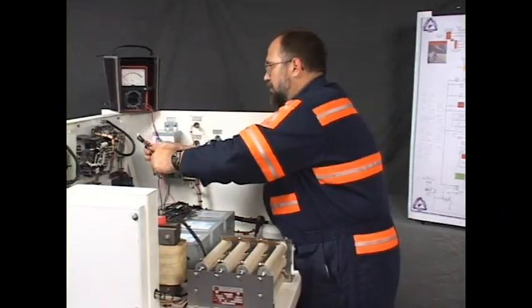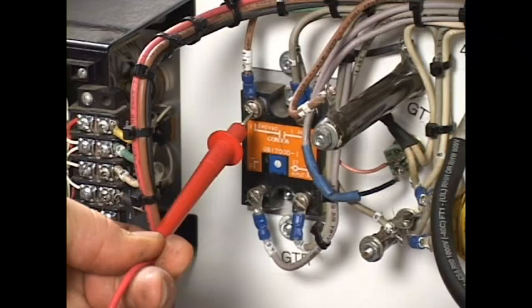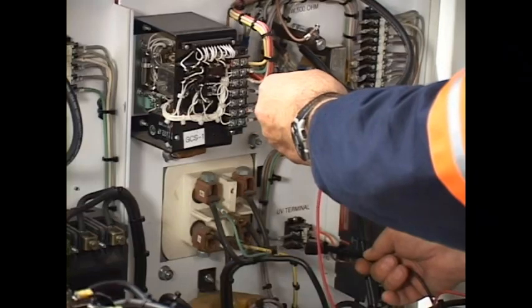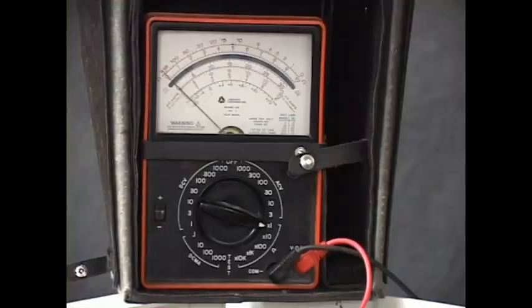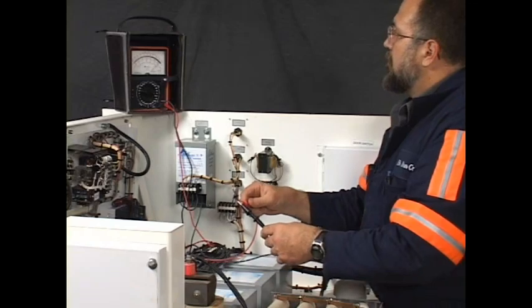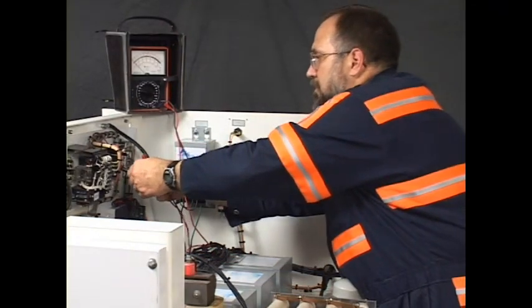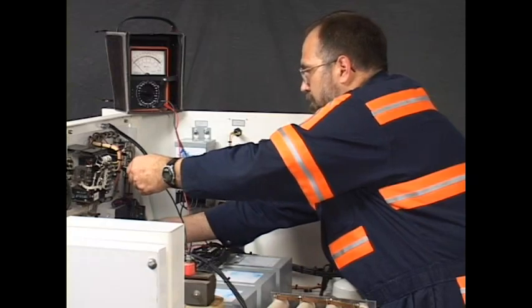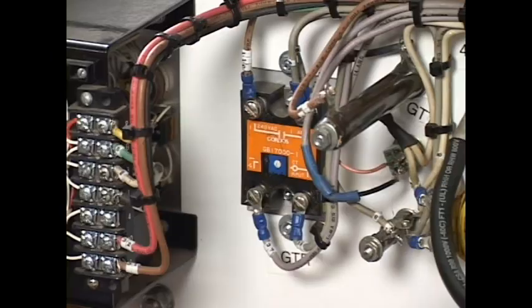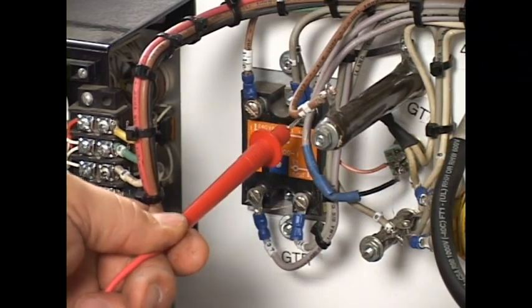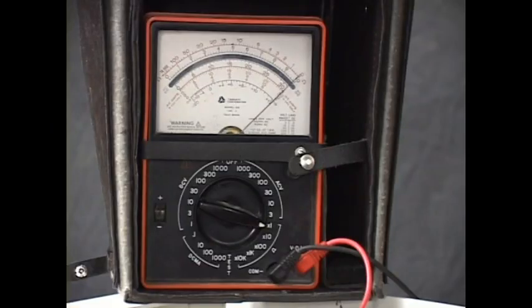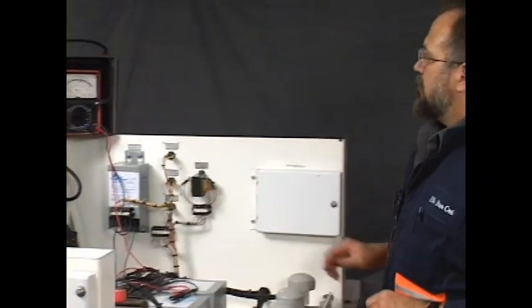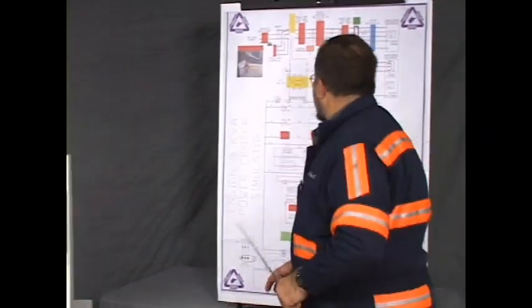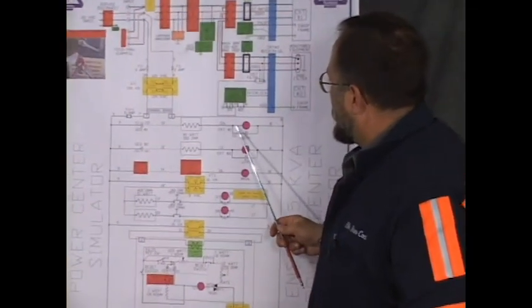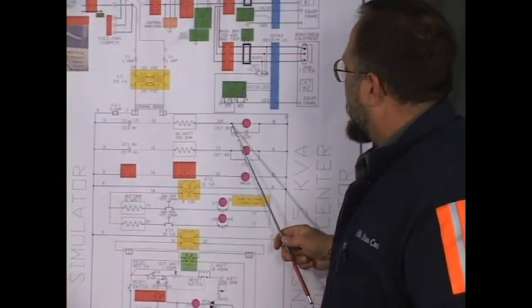Now, I'm going to begin by reading the wire 11 from the contacts of the ground trip relay to terminal 11 on the UV terminal block. It reads open. Let's check our meter. You frequently check your meter as you're troubleshooting. It still reads open. Well, let me read the other side of it just to make sure. Wire number 8 reads intact. Wire 11 reads open. Let's check our print here. This 11 from the UVR terminal block to the GTR contacts reads open.